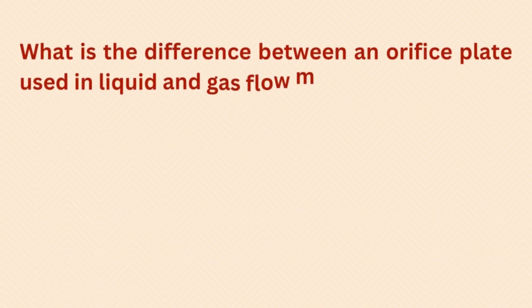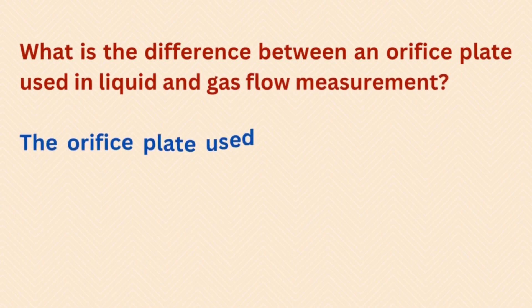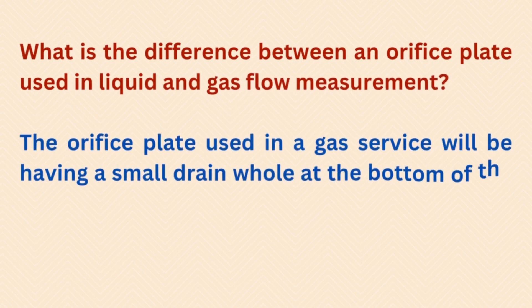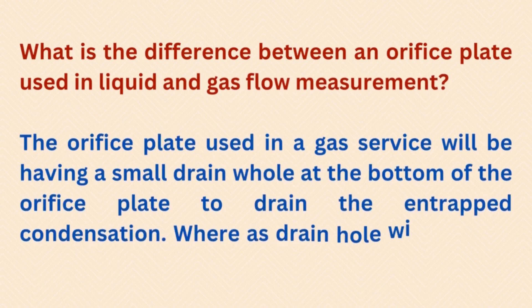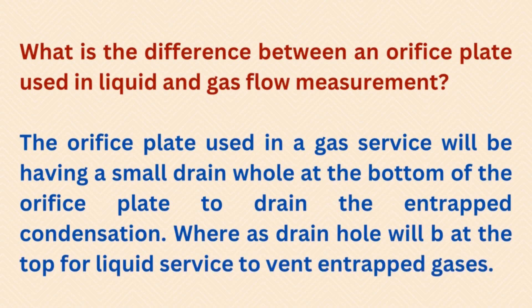What is the difference between an orifice plate used in liquid and gas flow measurement? The orifice plate used in gas service will have a small drain hole at the bottom to drain entrapped condensation, whereas the drain hole will be at the top for liquid service to vent entrapped gases.